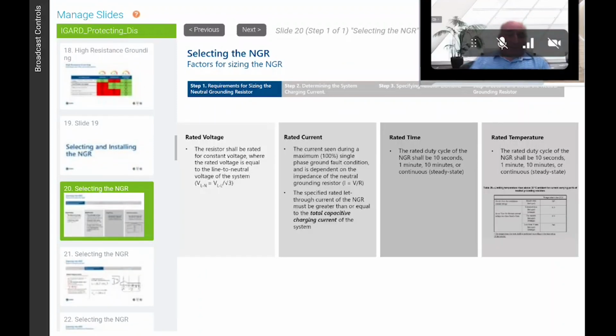So for selecting a neutral grounding resistor, we have to do a couple of things. First, we have to look at the rated voltage. A 5 kV system is 4160 volts, so for 4160 volts your line to neutral voltage is 2400. If you want to limit the fault current, you have to look at the rated current; the maximum is 100 amps. Basically, the resistor is equal to the voltage divided by the current you want to limit the fault to. So if you limit the fault current on a 5 kV system to 5 amps, you need a 480 ohm resistor: 2400 divided by 5 is 480 ohms.